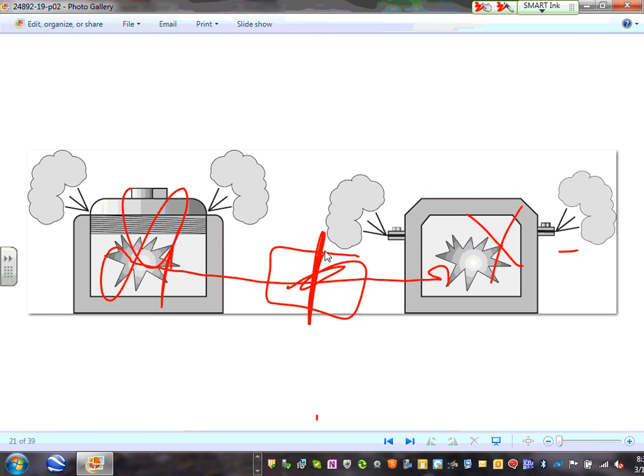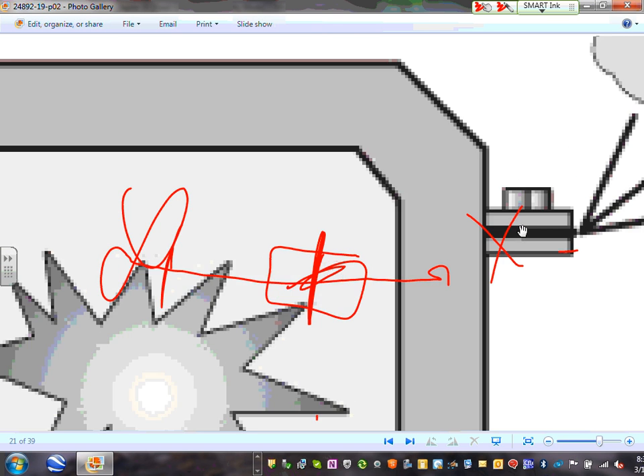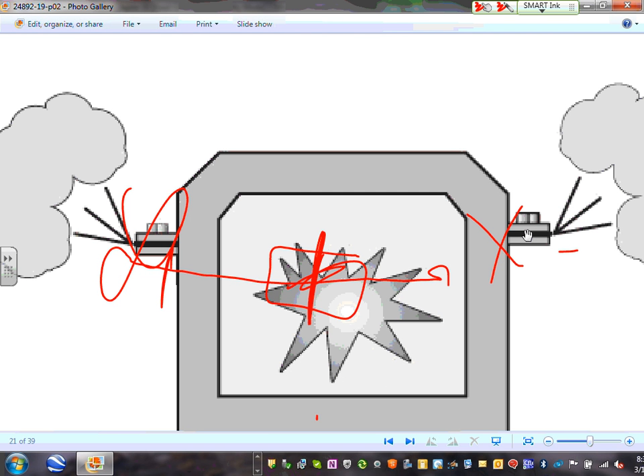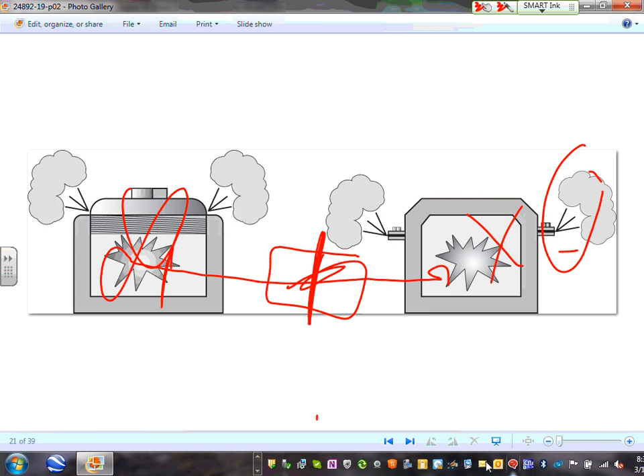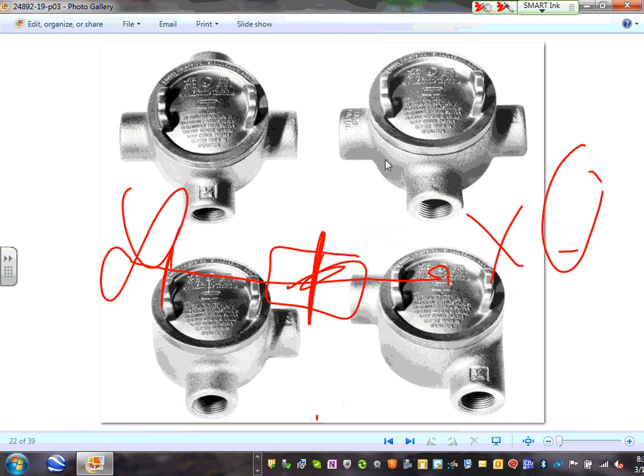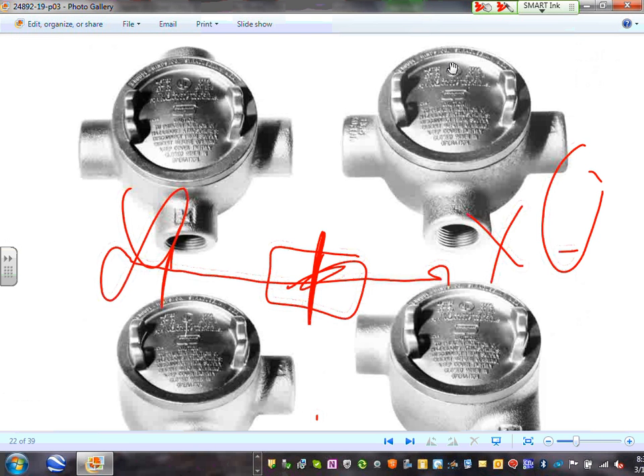So everything is, they allow the system, if you have an explosion, to release the gas. If you look at that, if you have an explosion inside it, there's a lot of threads, guys, that the gas will go right through the threads. At the time it enters here, the temperature of the gas will be very low so that it would not ignite the surrounding. So that's how they control the vent of these equipments. Look at what they do. These are junction boxes, guys. Unlike the junction boxes like I use right here, all threaded.